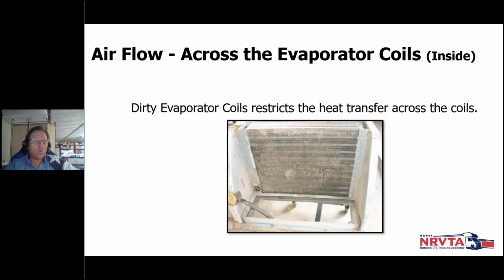All it took was some no-rinse coil cleaner. You spray it on there and it foams up, kind of like when you used to clean ovens, spraying that foam on the walls and it would bubble, then you'd wipe it off. You do the same thing here with the no-rinse coil cleaner, which you can buy at Home Depot, Lowe's, or similar big box stores.